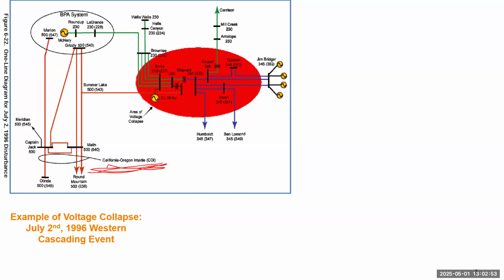In the August event, there was oscillation across this intertie, which caused the collapse of the entire system into four to five islands. Then there was a blackout of the Western interconnection. One month earlier than that oscillation event, there was a voltage collapse event. This is the boundary substation between the state of California and the state of Oregon.